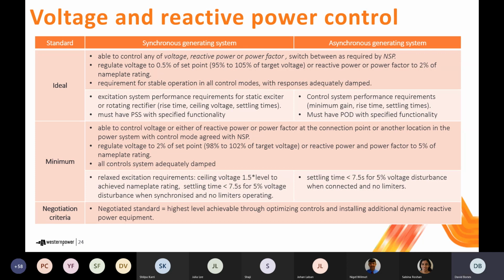And again, there's the requirements for technology-specific measures around the controls performance. So excitation system requirements for generating systems and control system requirements for asynchronous generating systems like inverter-connected solar farms. And this is an example of a standard where there is also a negotiated standard. So in this one, you're expected to achieve the performance which is possible through optimizing controls and, where practicable, installing additional dynamic reactive power equipment.